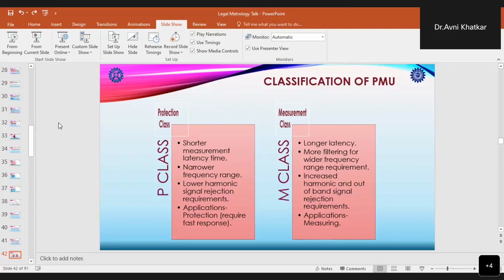However, the M class PMUs are the measurement class PMUs which are required for applications that deal with measuring. So they have longer latencies, and they require more filtering for wider frequency range requirements. In this, we have increased harmonic and out of band signal rejection requirements, and these PMUs are used basically for measuring applications. So basically PMUs are of two types, P class or M class, based upon their application in the grid.